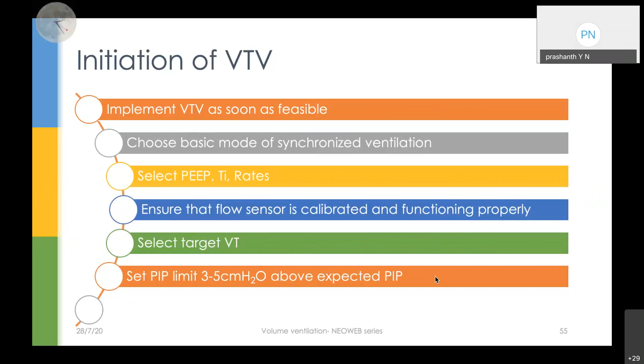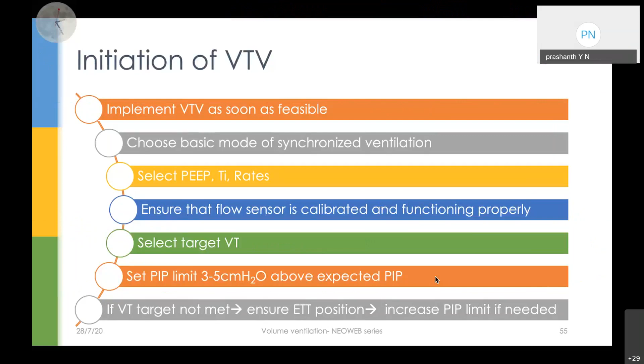So set the VT based on the disease pathology which we just discussed in the previous slide, and then a PIP limit of 3 to 5 centimeters of water above the expected PIP. So if I expect the baby's peak inspiratory pressure to be 16 to 18, I am going to set the maximum PIP 3 to 5 centimeters above that. After we start, we need to check whether the tidal volume target is being achieved and whether the position is correct, whether it is too high. If my position is correct, then I will have to increase my peak pressure, because the pressure needed to inflate the lungs probably reflects the resistance.